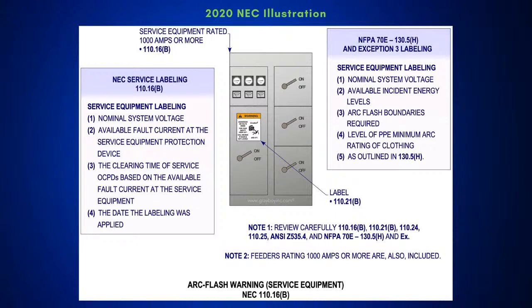But hey, I just have kind of a stupid question about this. Where would this be required to be applied? Just in general, would we have to do this at a dwelling unit service? No. No, this is for service equipment rated 1,000 amps or more. And that's it? Is there like a 110.16(A) that says other? Yeah, yeah. I'm just going through an example here. I'm not going through everything. Okay. I was just wondering because I know sometimes in dwelling units, you're not required to have an arc flash sticker. Well, it specifically says other than dwelling units.